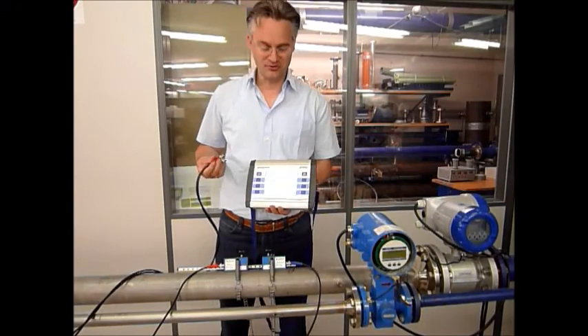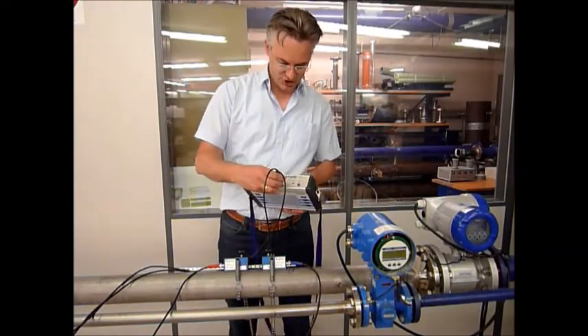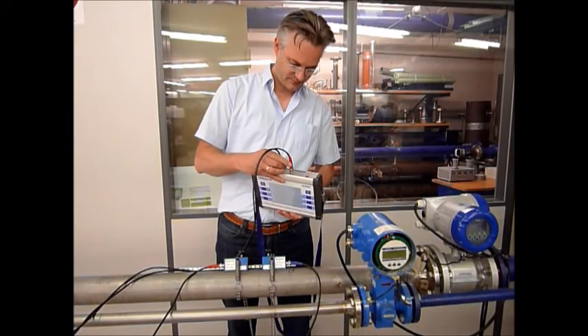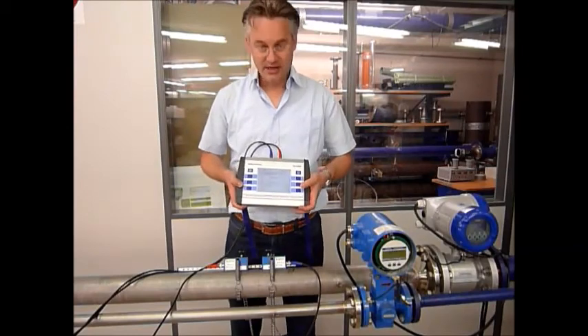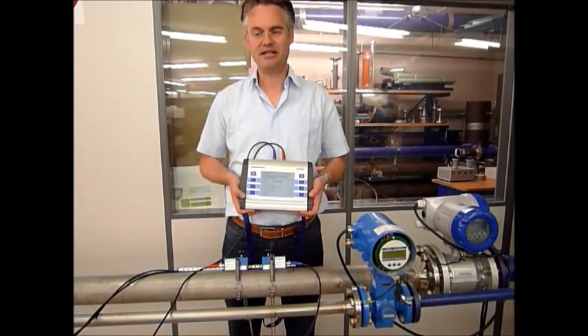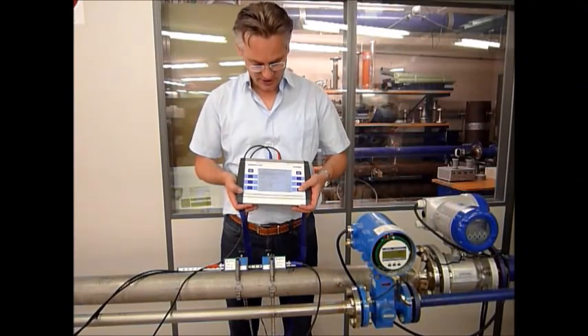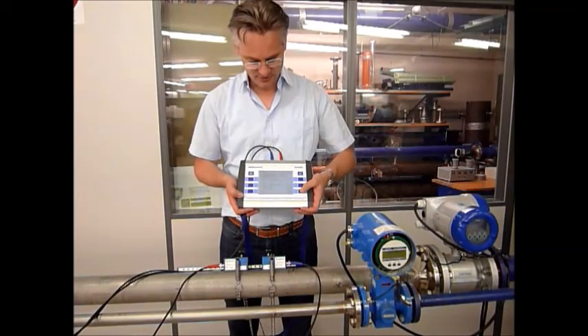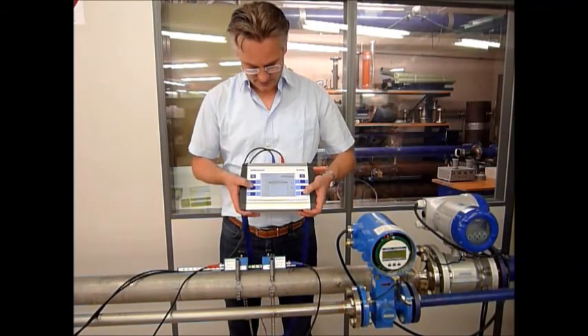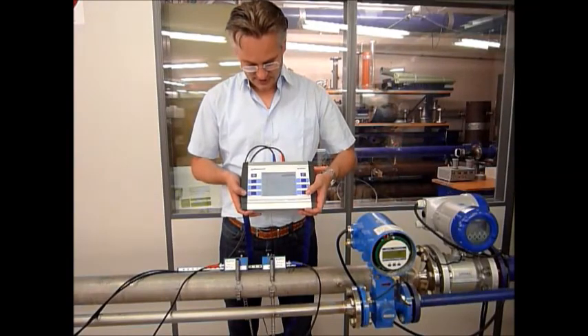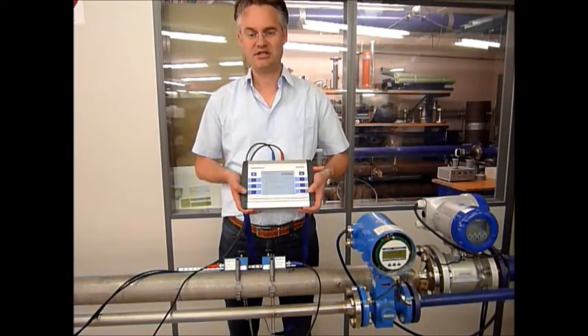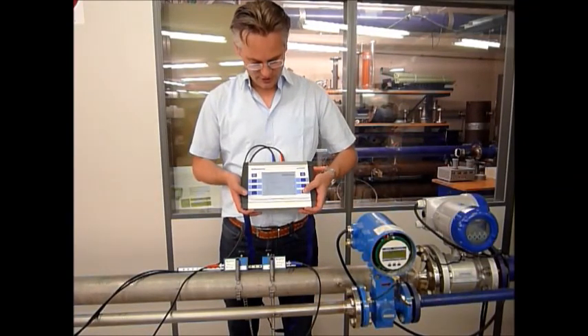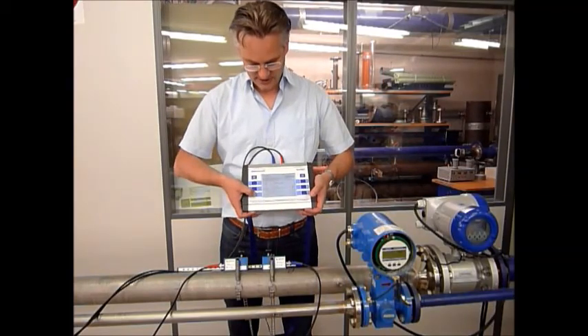We are almost ready now. Connect the cables with the flow meter on the back side of the housing with the BNC cables. If you have the possibility to do a zero offset calibration, this is recommended. Shut down the pipe and press the zero setting key. Within five seconds, the flow meter will do a zero calibration. This improves the accuracy, particularly for low flow velocities. After five seconds of integration, confirm the value and everything is ready for measurement.